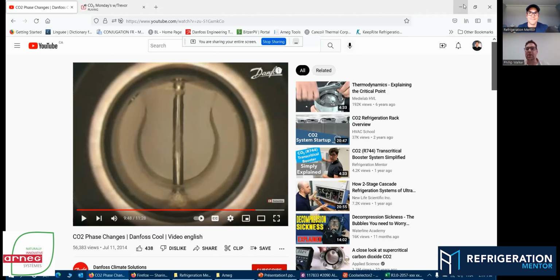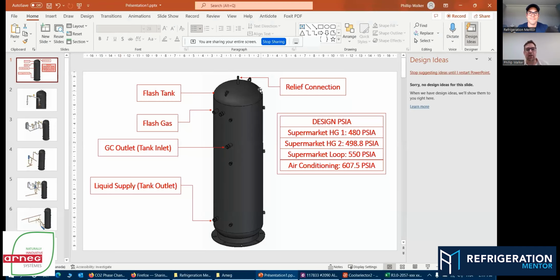And at the same moment, the job now of this tank, since we're flashing all this gas coming through, is to really regulate pressure and start having that gas condense inside in transcritical mode. So the little droplets of that gas coming back after that high pressure expansion device, which I have a photo of next, it's going to start to condense. You're going to have those little droplets form, fall down, and start pooling and creating your liquid.